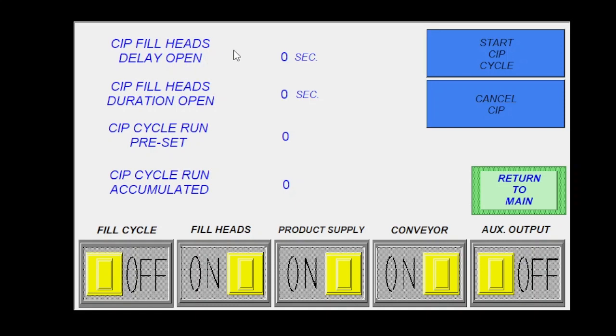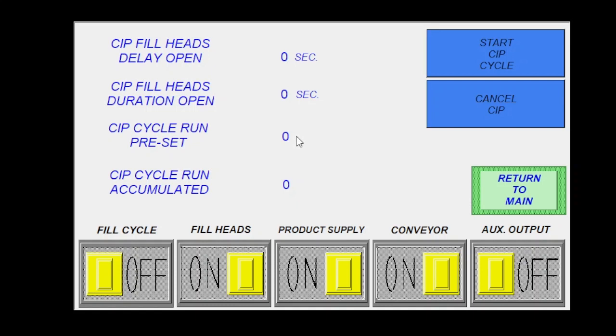So running a CIP, we have a separate video on the actual setup of all of this, but essentially you're going to program how long you want to delay the heads opening and how long you would want them to stay open in between each one of those delays. So the CIP will essentially pulse the fill heads open and closed while running the CIP spray ball that's in the tank.